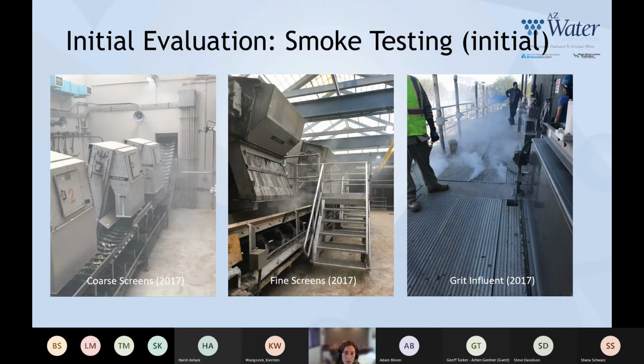So we performed smoke testing at the influent junction structure just upstream of the coarse screens, the screw pump inlet and outlet, and in the fine screen influent channels. We did this by lowering a smoke bomb in a bucket into the channel, allowing smoke to disperse and follow that foul air flow.